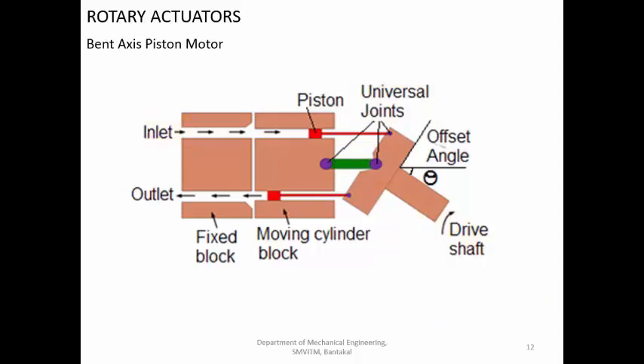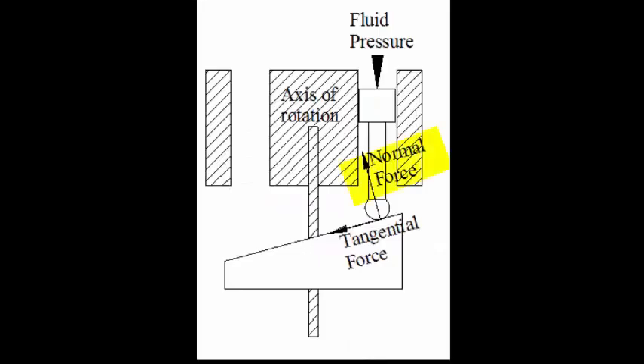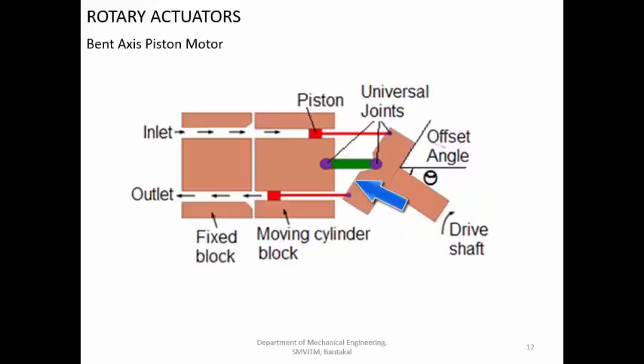When you supply high pressure fluid at the inlet, the piston is pushed outward. But the piston cannot move straight because it is applying force on the inclined surface — you are having a normal force and a tangential force to the surface. This tangential force causes the piston along with the cylinder block to rotate. This rotation is transferred by the universal joint from the cylinder block to the output shaft, and the output shaft will rotate about its axis. Simultaneously the cylinder block also will be having rotation.